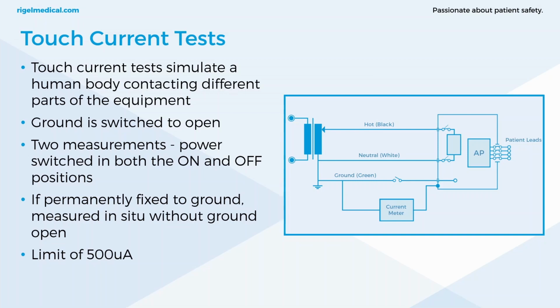Now, touch current tests simulate a human body contacting different parts of the equipment. It's any current that would flow from the equipment chassis, or any accessible parts that are not intended for patient care, so not patient leads, through a person. It applies to all portable equipment, and unlike 60601, there are no different fault conditions. It's just that the ground switch is open. Touch current tests simulate a human body contacting these different parts of the equipment, and the measured leakage current values are just checked to see whether they're within acceptable limits, which is 500 microamps.